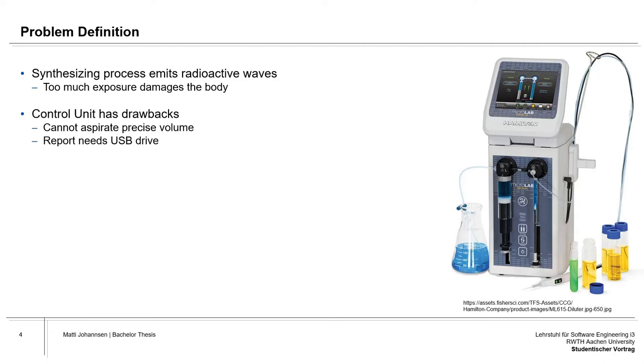Additionally, the control unit which is used for the control of the base unit has a couple of drawbacks. For example, the user cannot aspirate a precise volume if this volume lies below the maximum capacity of the used syringe. Furthermore, it is rather tedious to get, for example, every report PDF from the control unit because it is necessary to use an external USB drive.